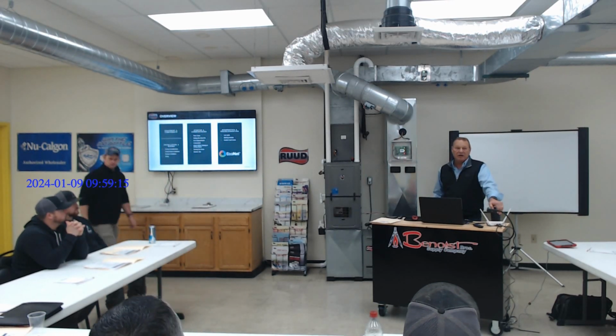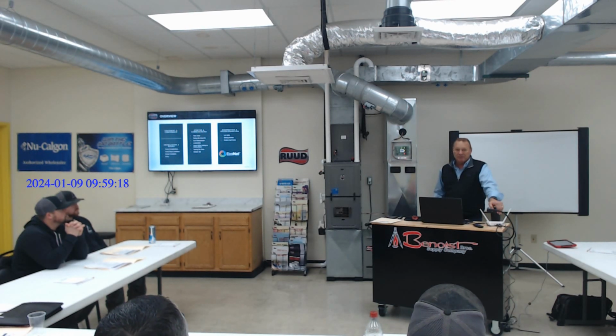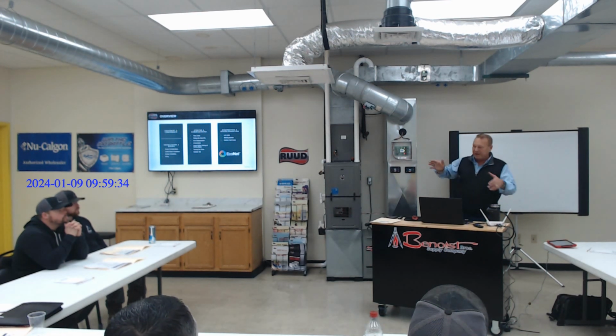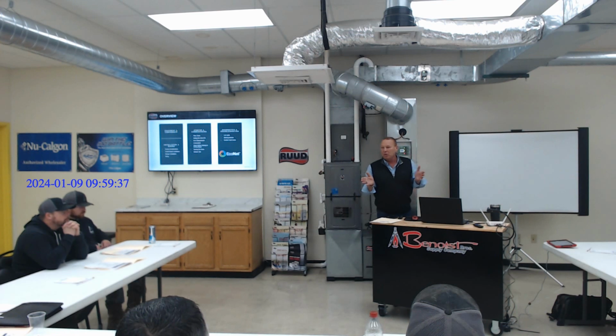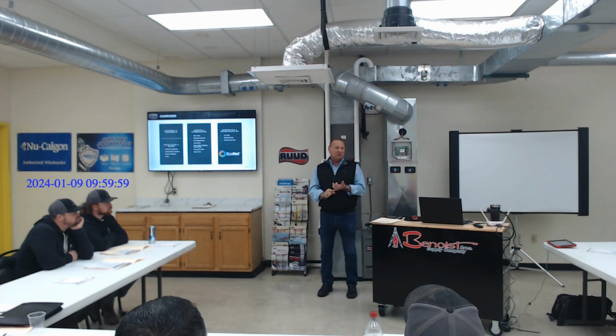Basically, if I'm looking for 1,000 CFM, as that motor ramps up, the CFM's not gonna change. If it says I want 1,000 CFM, that motor's looking for that torque on that shaft that says I'm moving 1,000 CFM, and it's gonna keep increasing the motor speed. So when these came out in '97, or '96, whenever these came out, the big deal was that these motors will overcome crappy ductwork, which was nothing but BS. It doesn't overcome anything. It just tries to keep achieving that CFM value across that coil or across that heat exchanger. Now, the second question I have for everybody is, does anybody know how many CFM for 10,000 BTUs of heat you need to keep a 90% furnace operational without tripping a limit?